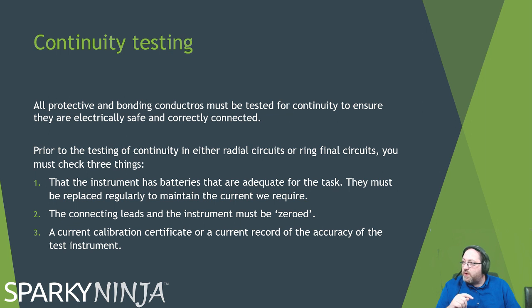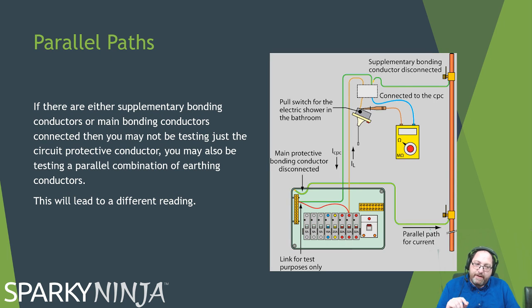So we need to remember as well with continuity testing is the parallel. Now if I have a piece of equipment that has, let's say I have my connection in the board and there's a connection to the water pipe, and that water pipe goes to the shower, and for some reason there's a cable from the pipe into the earth on the shower. I don't know why, but that's what's illustrated here. If I then test the continuity of the earth from the board to the shower and that is broken, the parallel back would give me a false reading. So I must always do these tests and disconnect parallel paths as best you can. Always be aware of parallels.